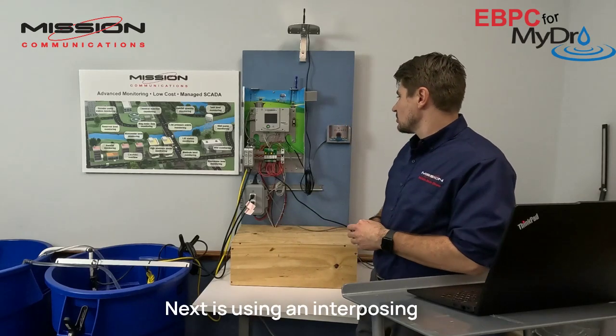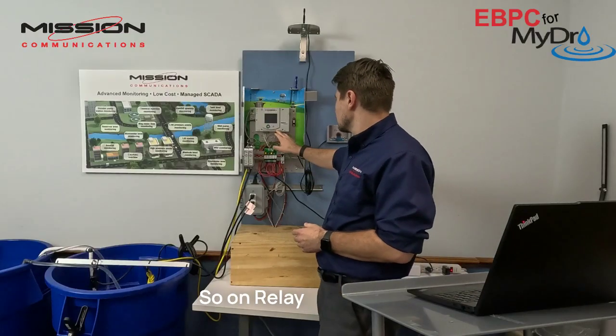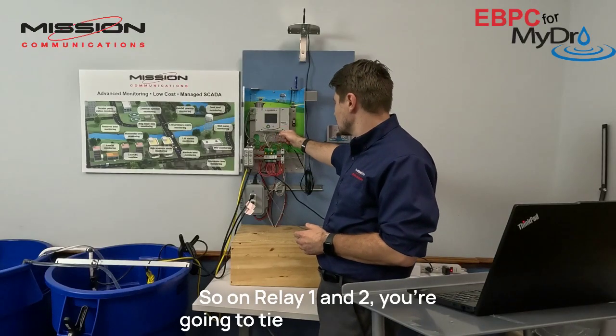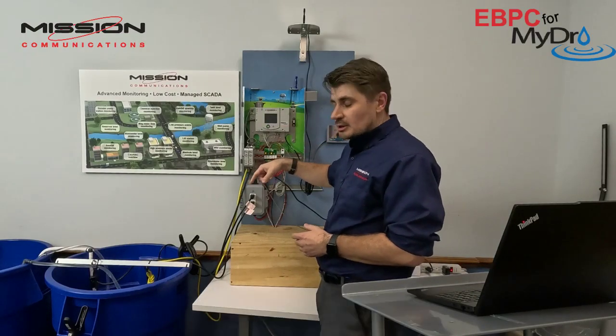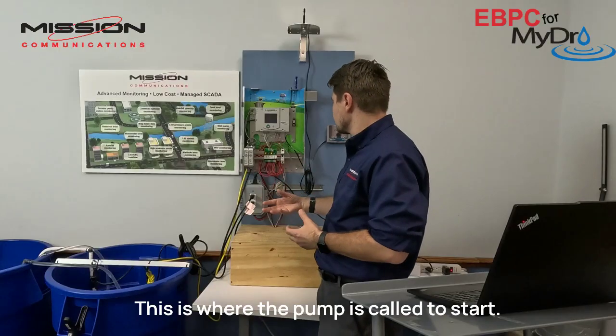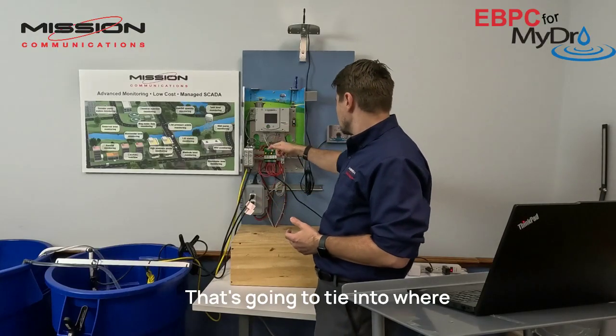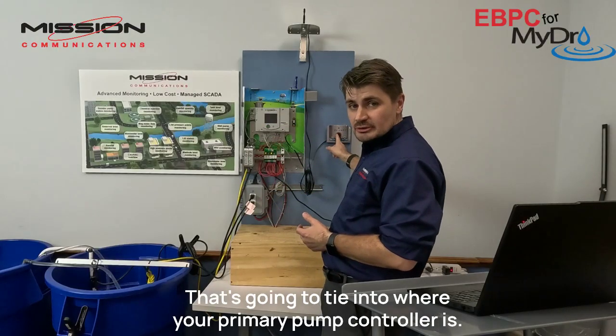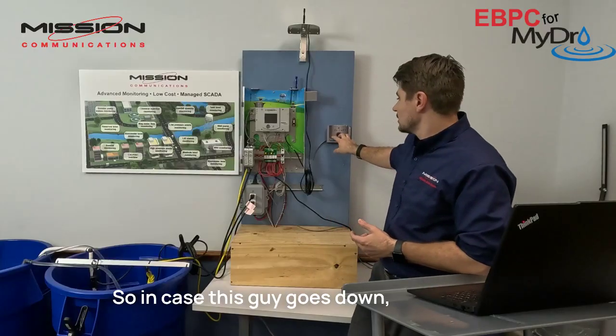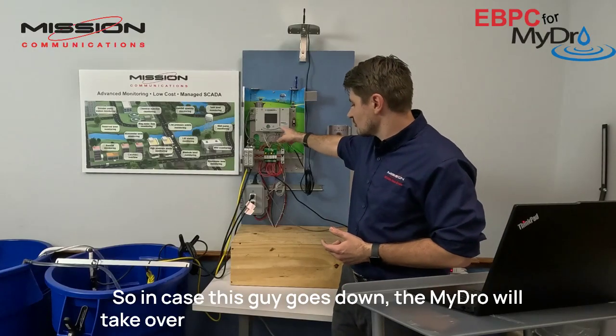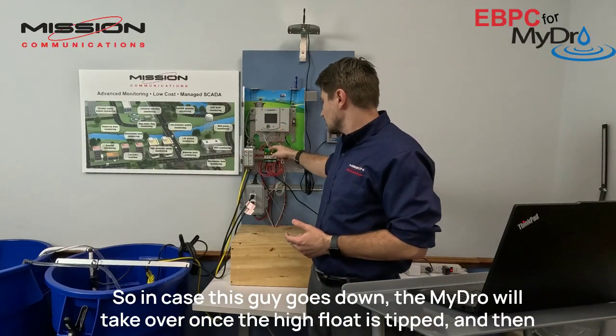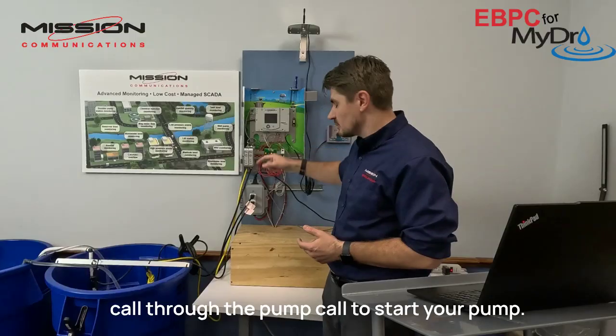Next is using an interposing relay. So on relay 1 and 2, you're going to tie into the pump call. This is where the pump is called to start. That's going to tie into where your primary pump controller is. So in case this guy goes down, the MyDro will take over once that high flow is tipped and then call through the pump call to start your pump.